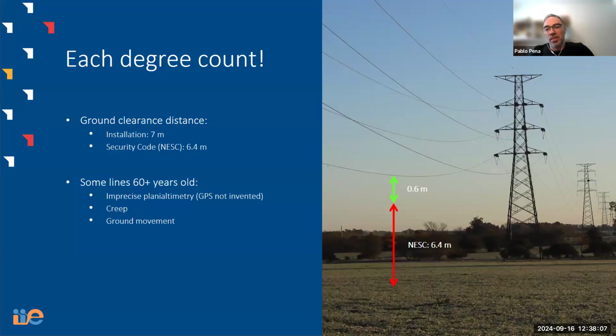Each degree counts. This could be the slogan for my tattoo, because every detail matters, and we work in that direction. Our lines were designed with a clearance of 7 meters, while the National Electrical Safety Code, the United States code that we use here in Uruguay as a reference, requires a minimum of 6.4 meters. That leaves us with a possible margin of 60 centimeters, enough to allow for an extra degrees, which translates to extra capacity.